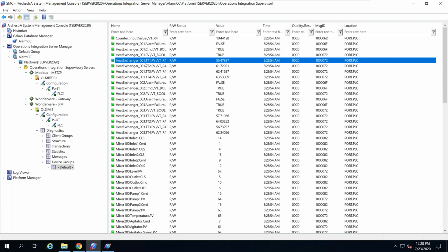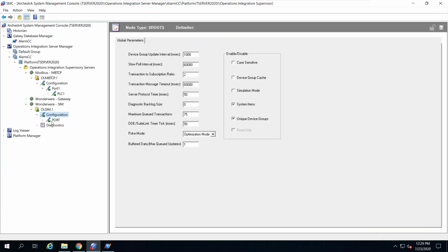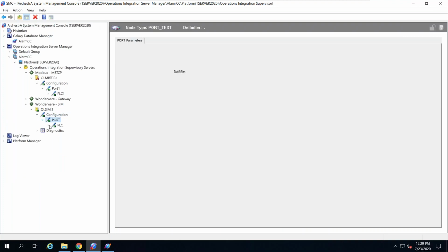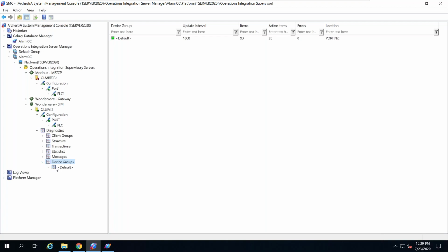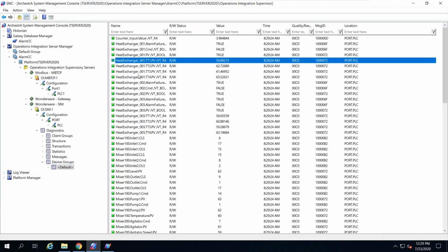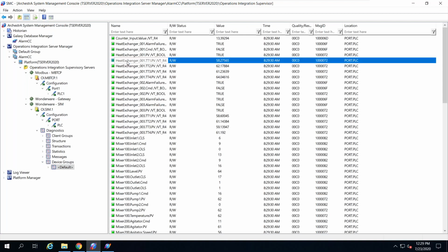Okay, if it's red, that means there is something missing from the server to the PLC. So you have to check the configuration from the PLC, or the configuration of your server itself. From here, you have to make sure about it. So if you have it red, that means I don't have any issue between the object and the server. The issue is from the server to the PLC. This is in general.